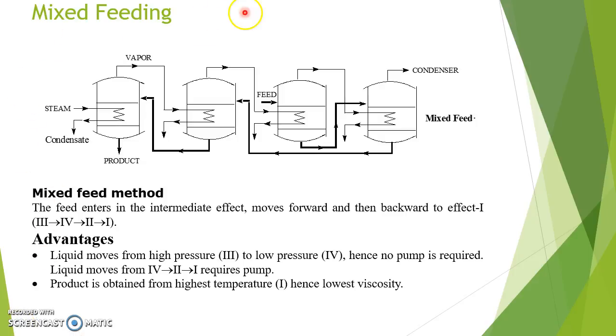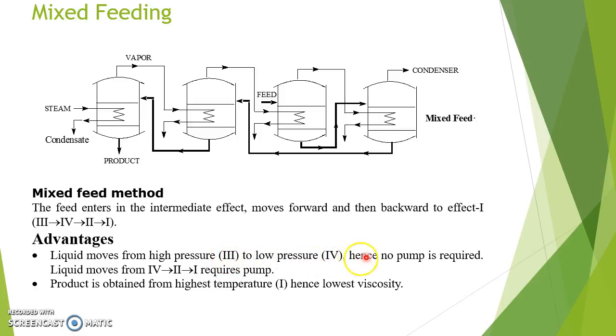In mixed feeding, the feed enters the third effect evaporator, then moves to the fourth effect, then to the second effect, and finally to the first effect. An advantage of this method is that liquid moves from high pressure to low pressure between the third and fourth effects, so no pumping is required there. However, liquid moving from the fourth to the second to the first requires pumping. The product is obtained at the highest temperature, hence with the lowest viscosity.